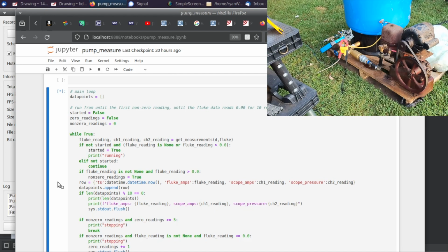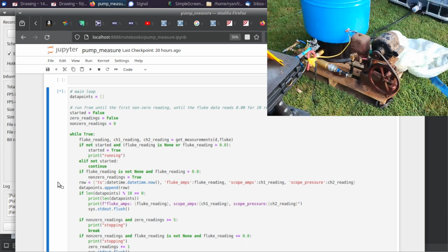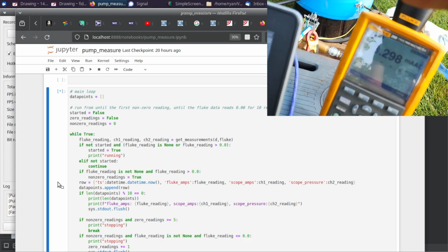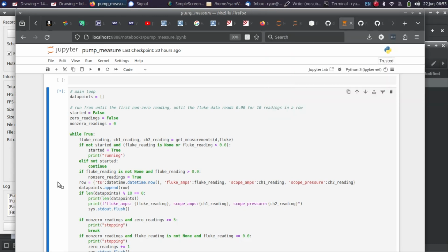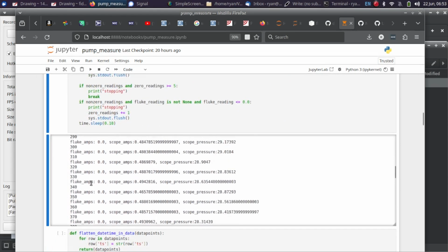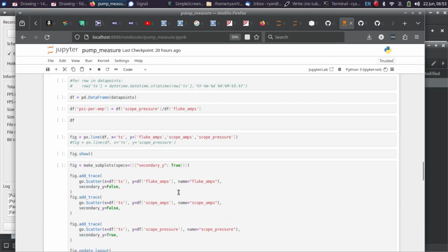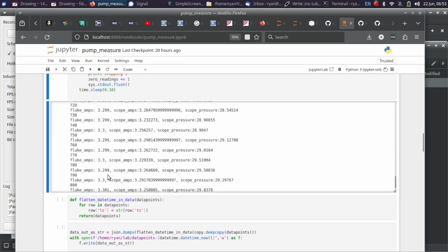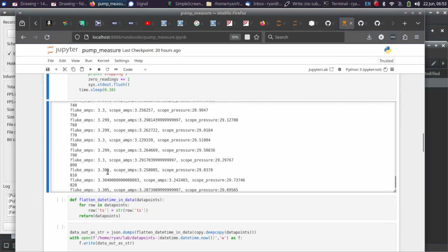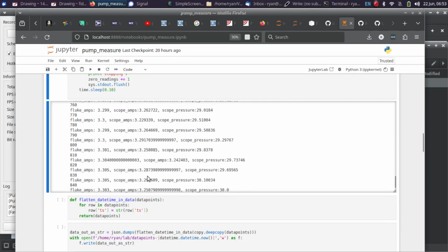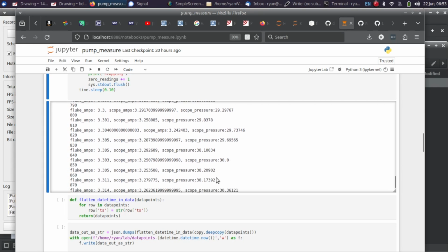All right, I've got the hose turned off, so we'll be able to see in the data the low point in the pressure and figure out when the valve was closed and we started our full cycle. You can see the Fluke is saying 3.3 amps. And then if we look at the screen recording, we can see what data is coming in. This prints every 10 iterations, so we can kind of see status as we're going here. So we got the Fluke amperage at 3.3, scope amperage just a hair lower, and then the pressure coming from the scope is 29 psi, 30.